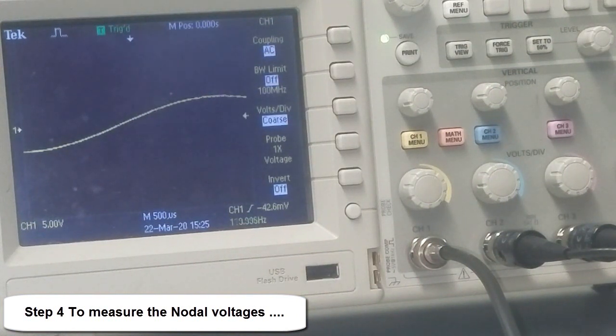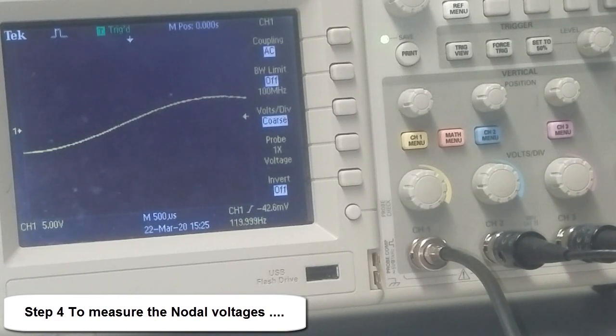The BNC to BNC is 1x because there is no division. There is no electronic circuitry to divide. However, if you're going to use those probes, the probes have electronic circuitry, and they divide by 10. I set them to be 10x. That means the probe divides by 10, so the scope needs to multiply by 10.